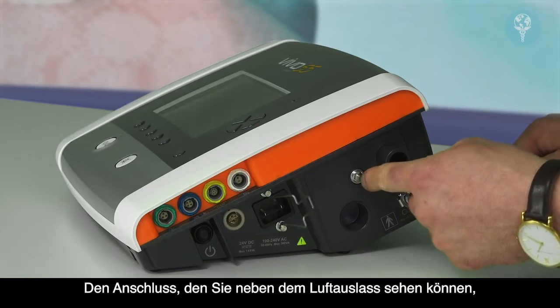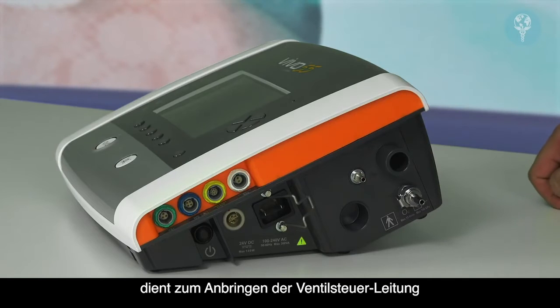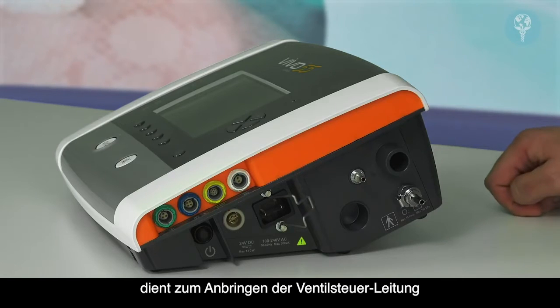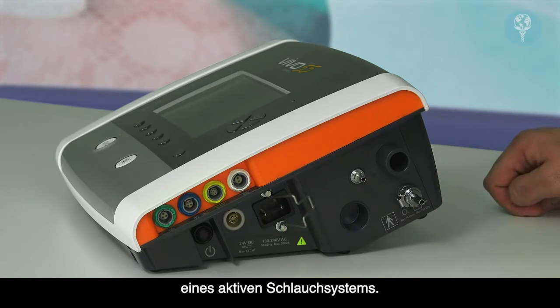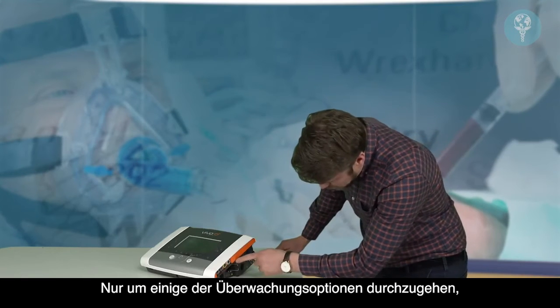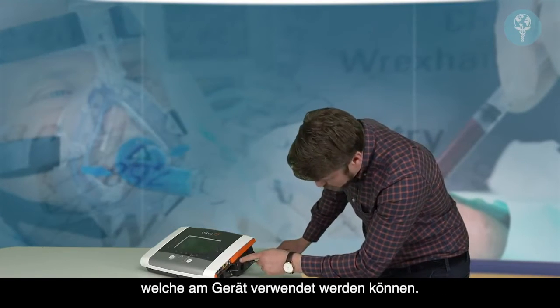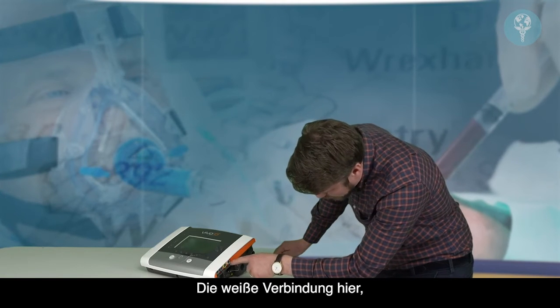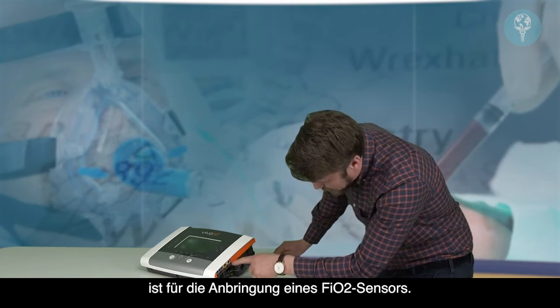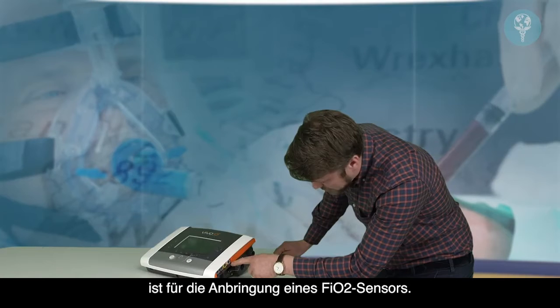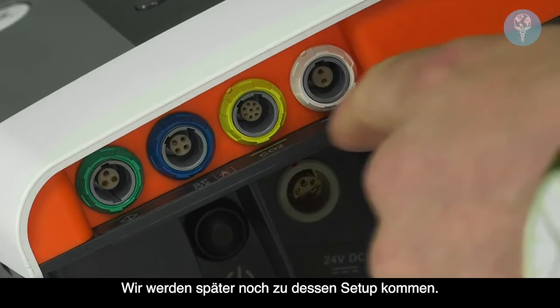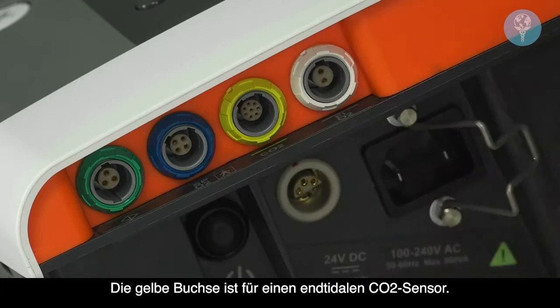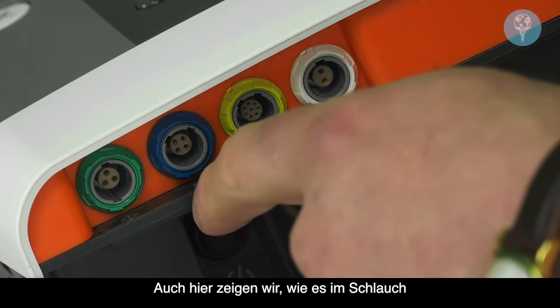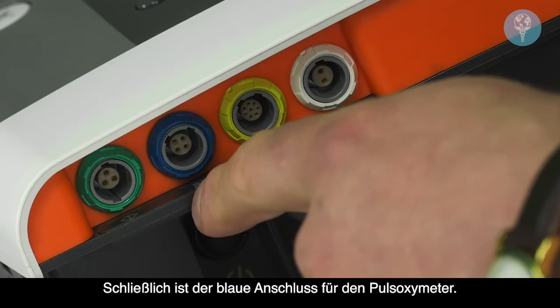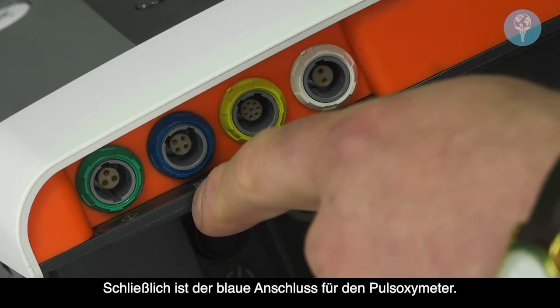The connection that you can see next to the air outlet is for attaching the proximal pressure line from an active valve circuit. Just to run through some of the monitoring options that will be used with the device. So the white connection here is to attach your FiO2 monitoring sensor. So again, we'll come to that setup a little bit later. The yellow connector is for your end-tidal CO2 sensor. So we'll see how to connect that into the tubing and back to the device. And then the blue connection is for your pulse oximeter.